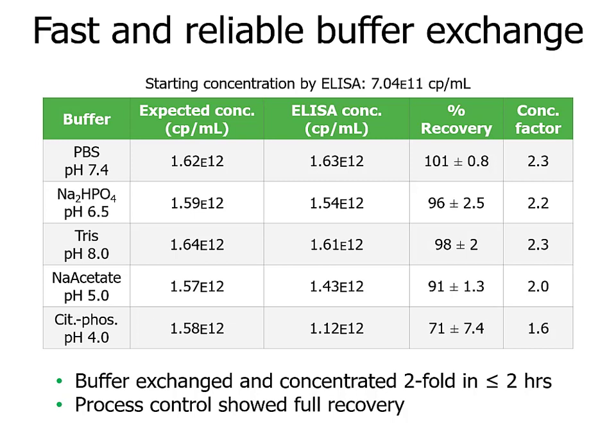Big Tuna was able to complete all of these exchanges and concentration steps in under two hours. We had about 100% recovery in our PBS process control, and similarly high above 90% recoveries for four of our five buffers, showing Big Tuna's high degree of reliability. However, the citrate phosphate buffer had a significantly lower than expected recovery, and we'll be able to look into why that happened in a moment.